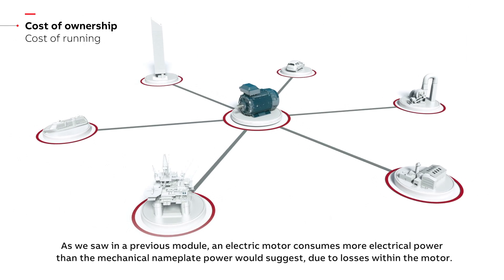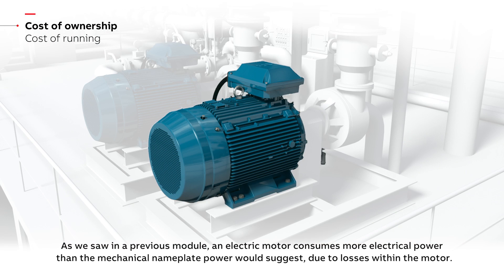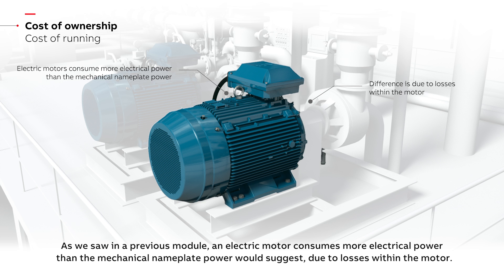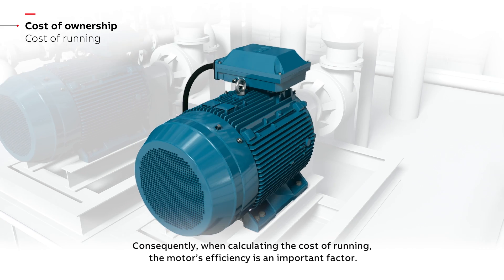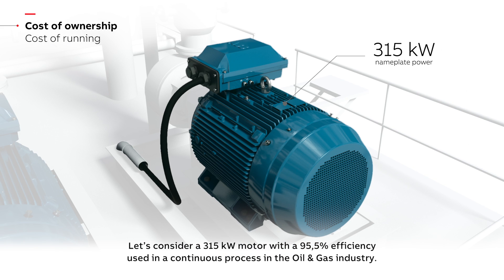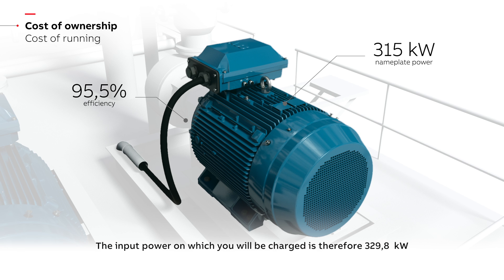As we saw in a previous module, an electric motor consumes more electrical power than the mechanical nameplate power would suggest due to losses within the motor. Consequently, when calculating the cost of running, the motor's efficiency is an important factor. Let's consider a 315 kilowatt motor with a 95.5 percent efficiency used in a continuous process in the oil and gas industry. The input power on which you will be charged is therefore 329.8 kilowatts.